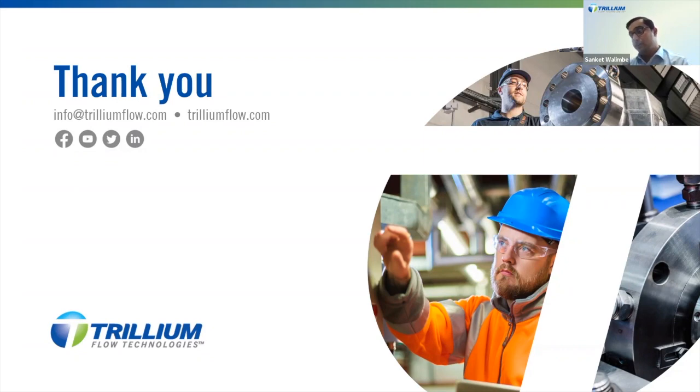Regarding the other design modifications, which are basically down to the engineering, these are straightforward design modifications, and the customer should not really be worried about them. However, the heat tracing element is quite critical. As long as the heat tracing is maintained adequately and avoids the crystallization of the salt, the performance of the valve will not degrade over time. So in short, it's very easy for the customer to implement these solutions, and we don't anticipate any major issues.